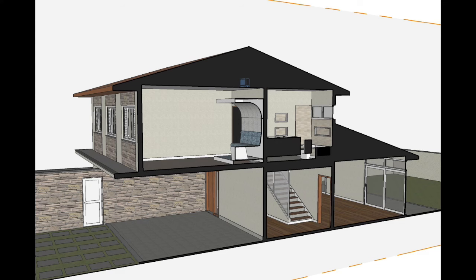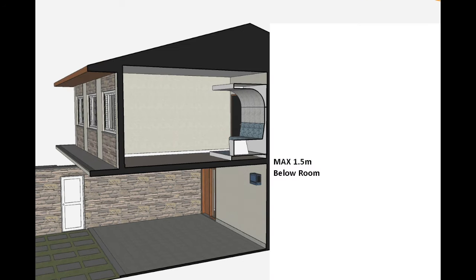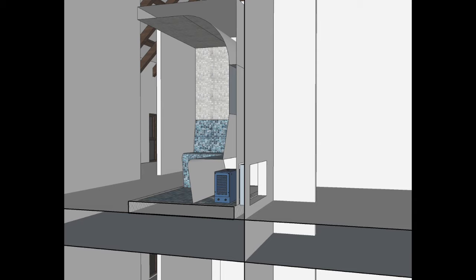Location: The steam generator can be installed in a number of locations. For example, in the loft or in a room above the steam room, below the steam room but no lower than 1.5 metres underneath the floor of the steam room, or under the benches of the steam room.